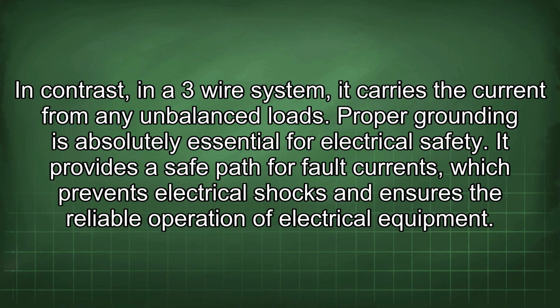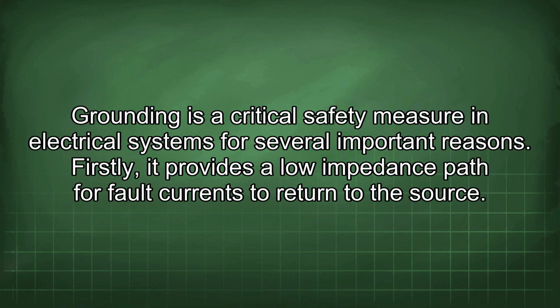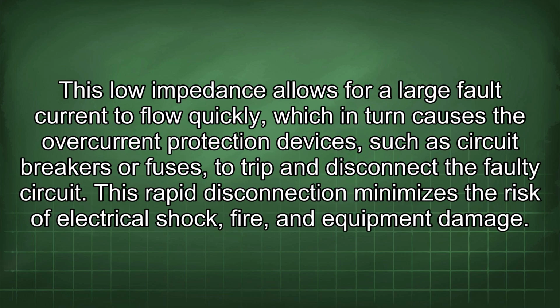Proper grounding is absolutely essential for electrical safety. It provides a safe path for fault currents, which prevents electrical shocks and ensures the reliable operation of electrical equipment. Grounding is a critical safety measure in electrical systems for several important reasons. Firstly, it provides a low impedance path for fault currents to return to the source. This low impedance allows for a large fault current to flow quickly, which in turn causes the overcurrent protection devices, such as circuit breakers or fuses, to trip and disconnect the faulty circuit. This rapid disconnection minimizes the risk of electrical shock, fire, and equipment damage.